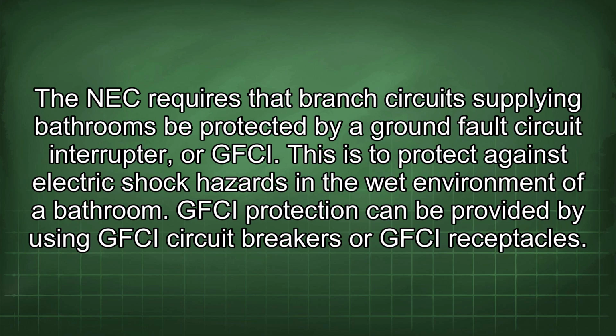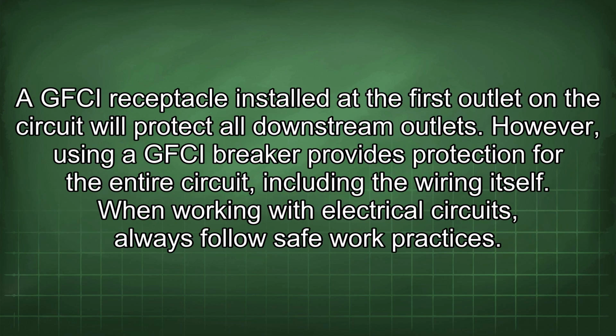GFCI protection can be provided by using GFCI circuit breakers or GFCI receptacles. A GFCI receptacle installed at the first outlet in the circuit will protect all downstream outlets. However, using a GFCI breaker provides protection for the entire circuit, including the wiring itself.